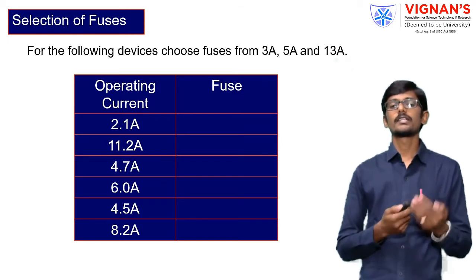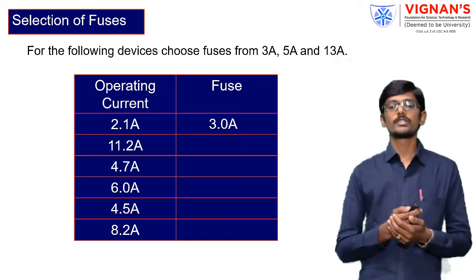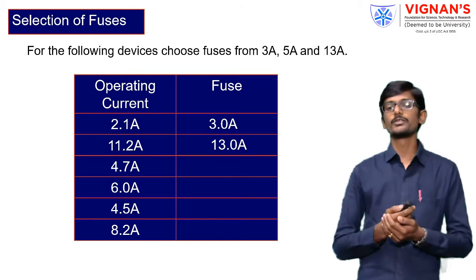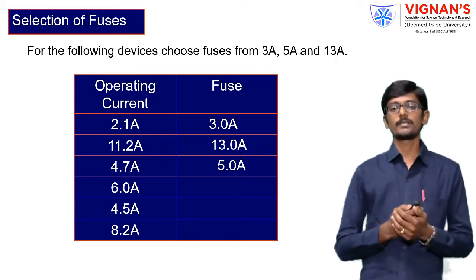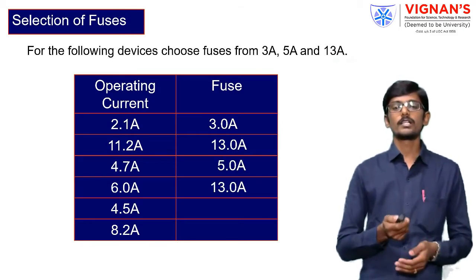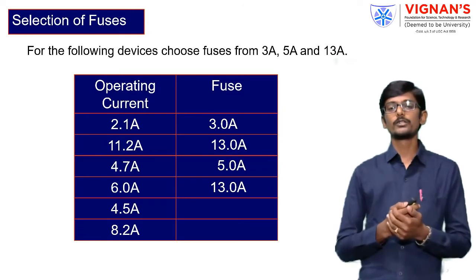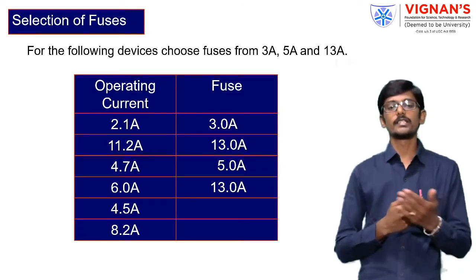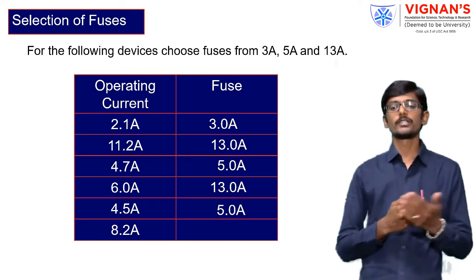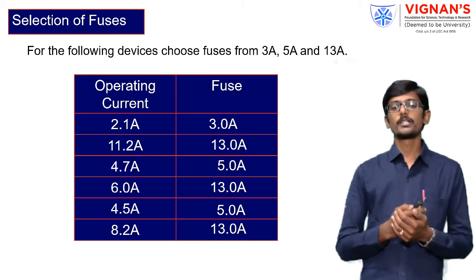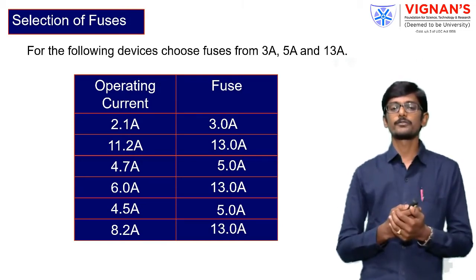For a current rating of 2.1 amps, we are going to use a 3 amps fuse. For 11.2 amps, we are going to use 13 amps. For 4.7 amps, we are going to use a 5 amps fuse, and for 6 amps, we are going to use a fuse rating of 13 amps. For 4.5 amps, we are going to use 5 amps. For 8.2 amps, we are going to use a 13 amps fuse.